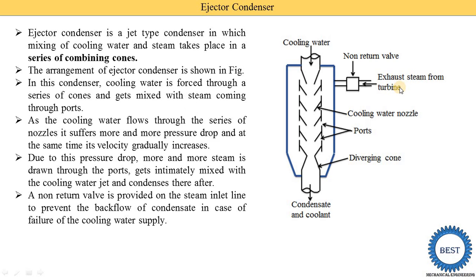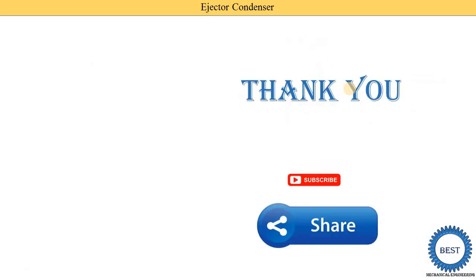In some cases the cooling water circulation is stopped due to maintenance of the pump or the pump is not working. At that time, the steam is not drawn in these nozzles and the condensation of the steam is not carried out. At that time, there is a possibility that the steam backs into the turbines. That's why the non-return valve is put here.